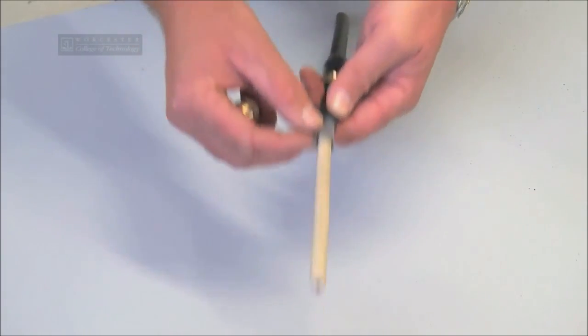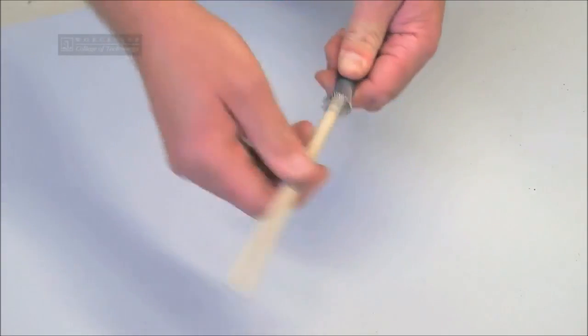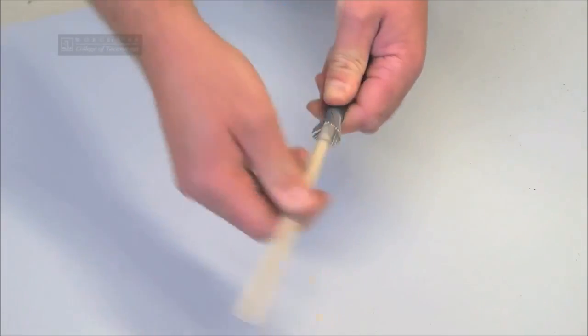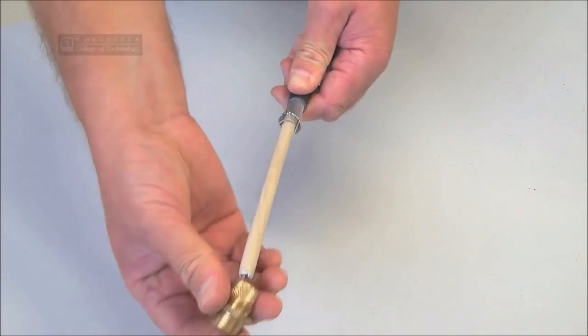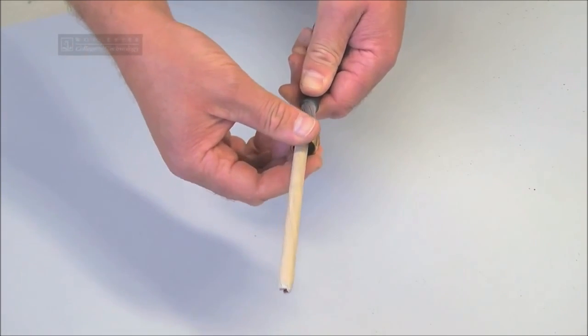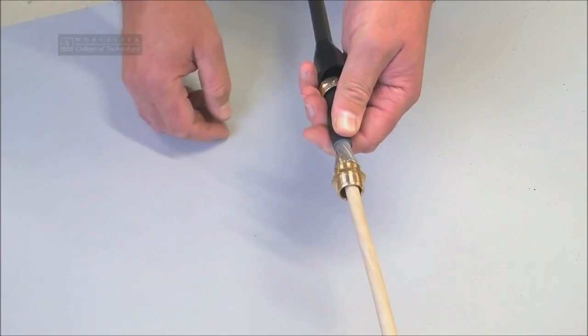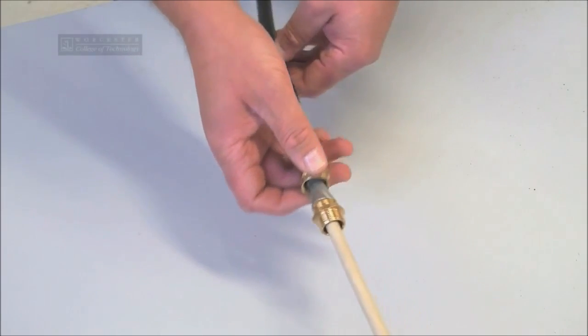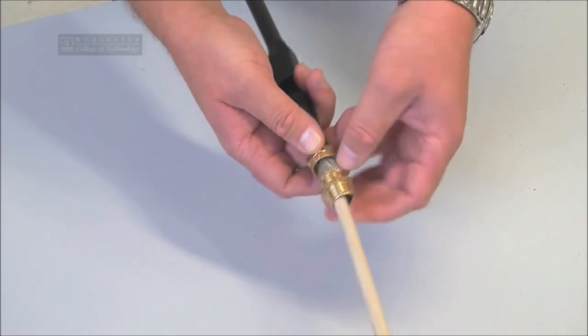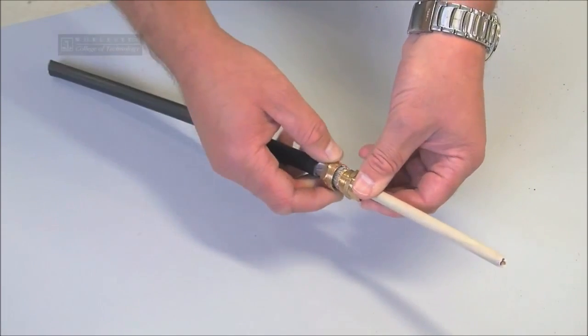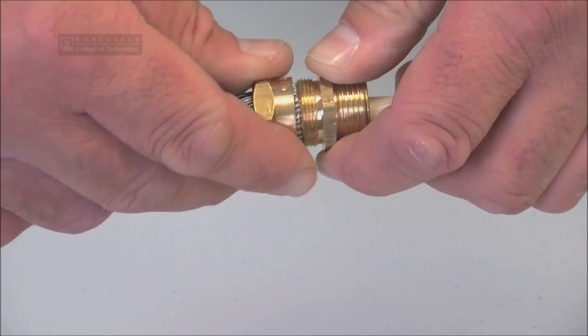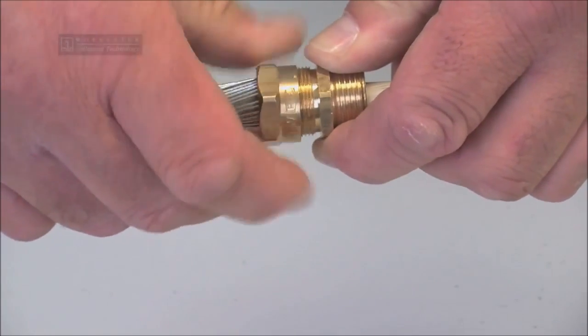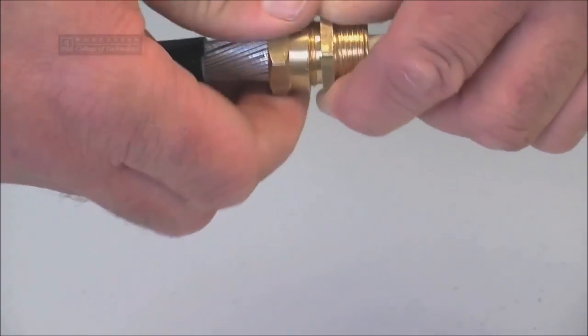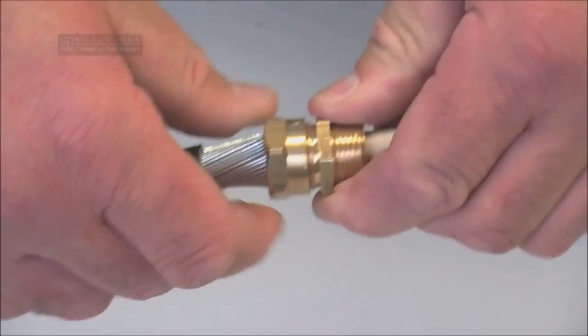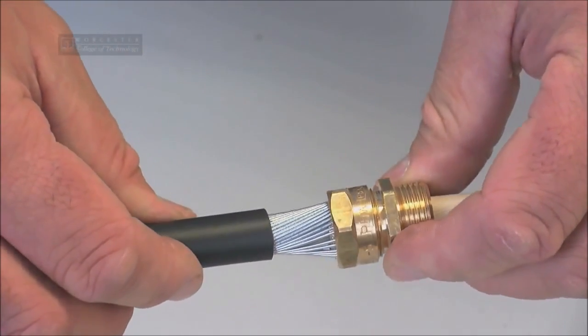In this case it is in a clockwise direction, and by rotating the cable in this direction, this makes it easy to fit the knurled section over the braids. We ensure that all the braids are on the knurled section of the gland. Bringing the top section over, we then tighten them up with our fingers and we ensure that all the braids are clamped between the locking nut and the knurled section of the gland.